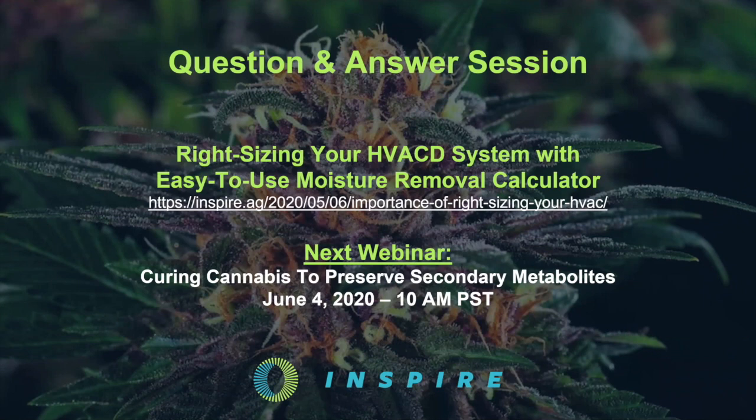When we talk about brute force, we're specifically talking about the use of a commercial air conditioner that takes the room temperature and humidity air and brings it all the way down past that dew point that's required to maintain the room condition. And that takes a lot of compressor energy. Compressor energy is 70 to 80% of most air conditioning systems. We try and reduce that using that air-to-air heat exchanger system or a coil runaround loop. And we've also looked at dry and liquid desiccants, and they might do a very good job too. Frankly, we haven't found much luck, but it's all about system design and thoughtful approaches ahead of time. Absolutely.